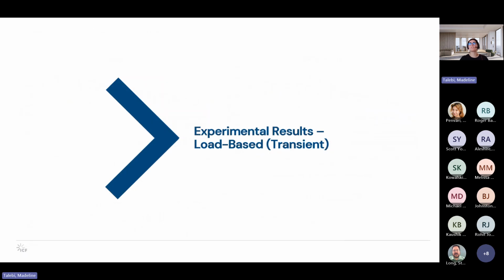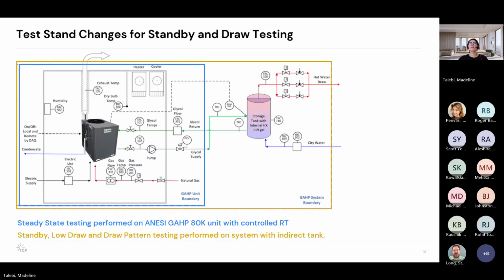So now that we've established our baseline, we can get into looking at some of the load-based or transient data. Before I get into that, I just want to mention something that GTI found when they were looking at configuring this. They did adjust this slightly. This is steady state testing that was performed on this unit with a controlled return temperature, as I mentioned, according to the test plan that was outlined at the beginning of this presentation. For the standby, low draw, and draw pattern, those 3 different part load test parameters that were set, the testing was performed on a system with an indirect storage tank. The storage tank was about 119 gallons with an internal heat exchanger.